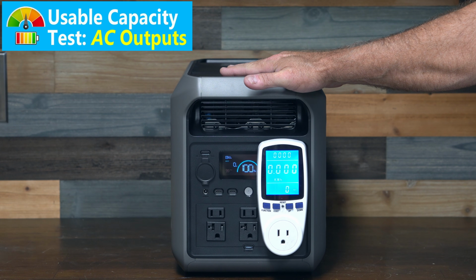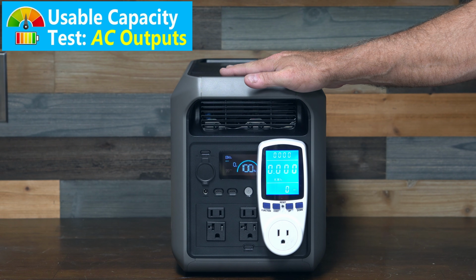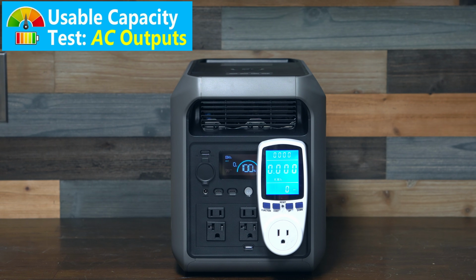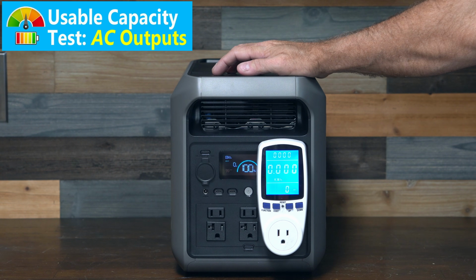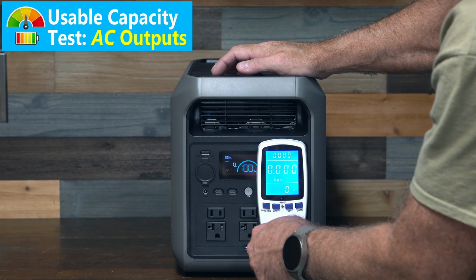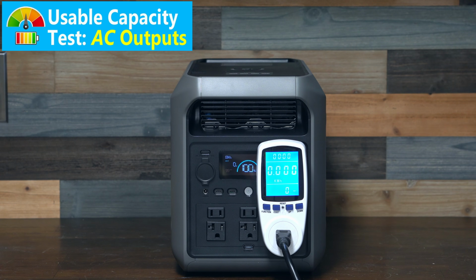So if we're going to do, or at least try to do, a 0.2C discharge rate, or 20% of the inverter capacity, that would equate to 440 watts. Now it's going to be kind of tricky to get it right at 440 watts, so I might have to play with this a little bit and see if I can find the best mix between 400 and 500 watts.